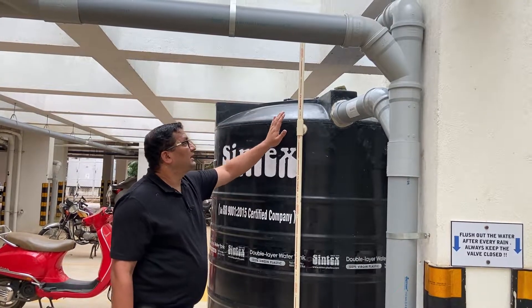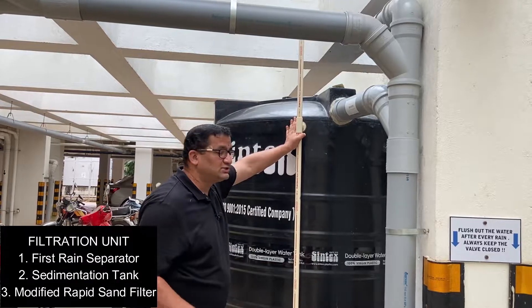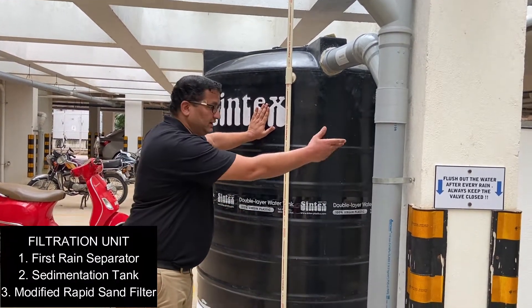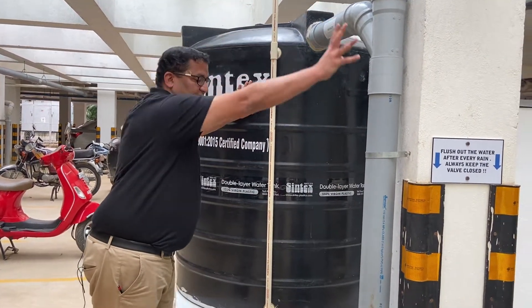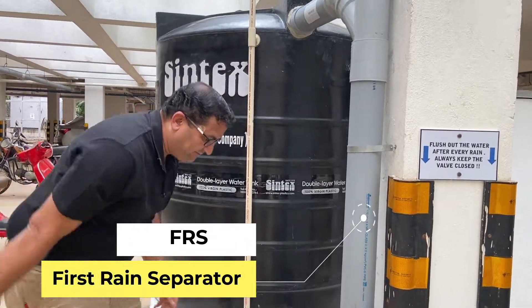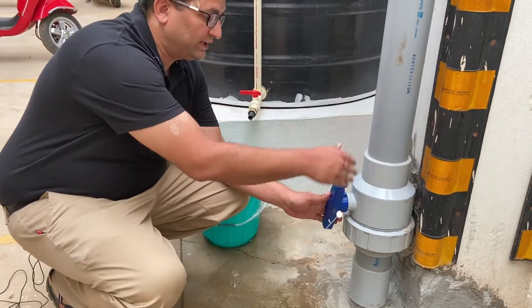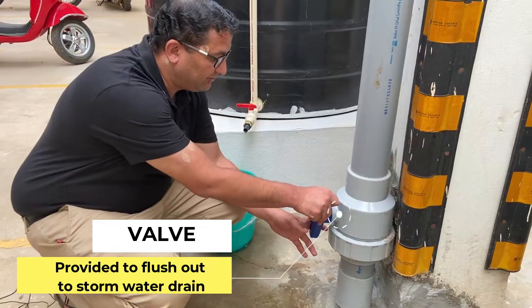The rainwater now gets into this filtration unit. The filtration consists of three parts: the first rain separator, the sedimentation tank, and the modified rapid sand filter. The rainwater first gets into this plumbing arrangement — this is called a first rain separator. There is a valve provided here. If this valve is open, the rainwater will go into the storm water drain and does not go into the filtration.